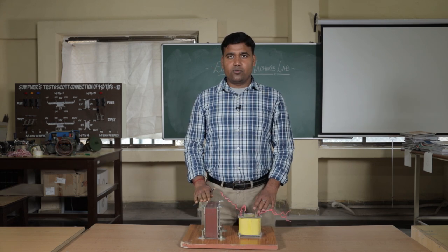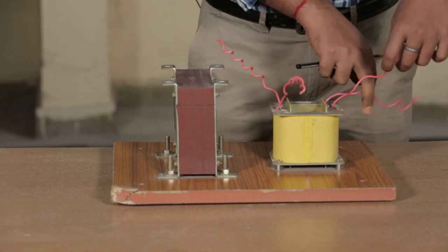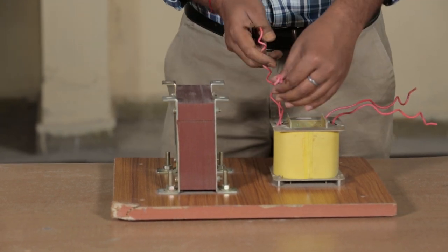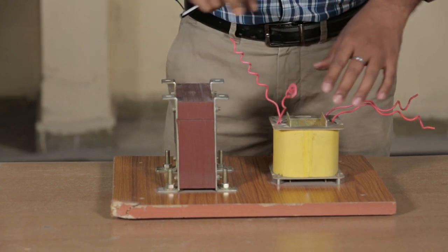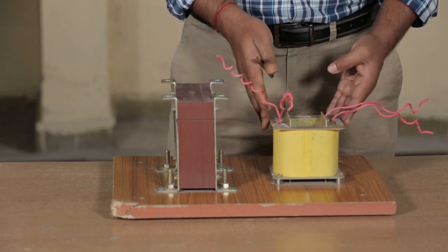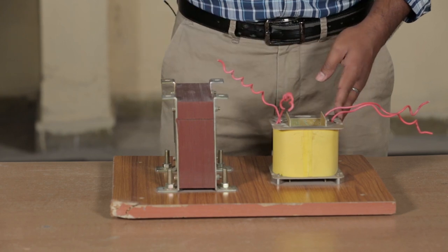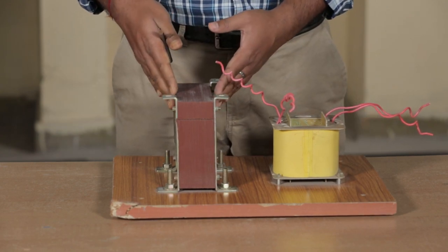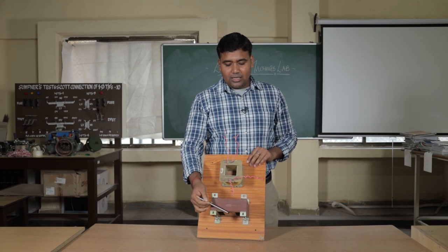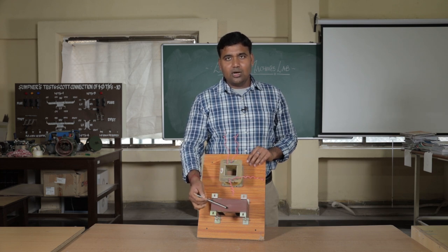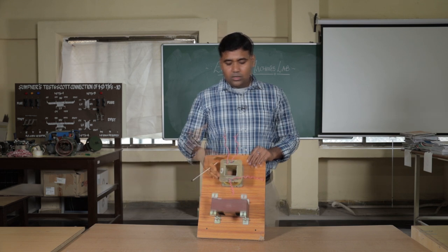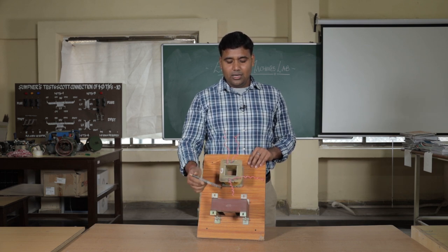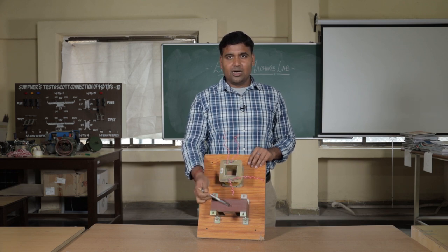This is the cutout section of a transformer. We can see two coils coming from the supply, which form the primary winding of the transformer. The load is connected to the secondary winding. If we have a three-phase transformer, three single-phase transformers are connected to a core. This is the core, which is basically an iron core. We can see laminations in the core to reduce the eddy current loss in the core.